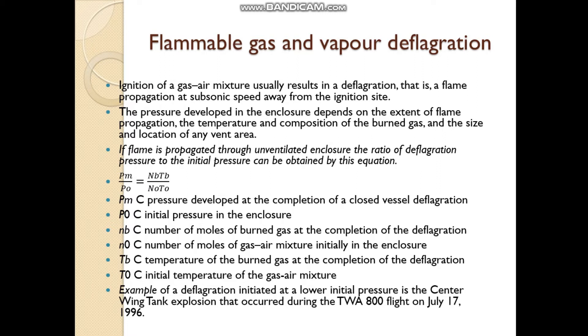The pressure which develops in the enclosure will depend on the flame propagation extent, temperature, the burnt gases and their composition, and the vent area — its size and location. For a closed vessel deflagration, the formula is: PM / PO = (NB / NO) × (TB / TO), where PO is initial pressure in the enclosure, NB is number of moles of burnt gas at completion of deflagration, NO is number of moles of gas-air mixture in the enclosure, TB is temperature of burnt gas at completion of deflagration, and TO is initial temperature of the gas-air mixture.